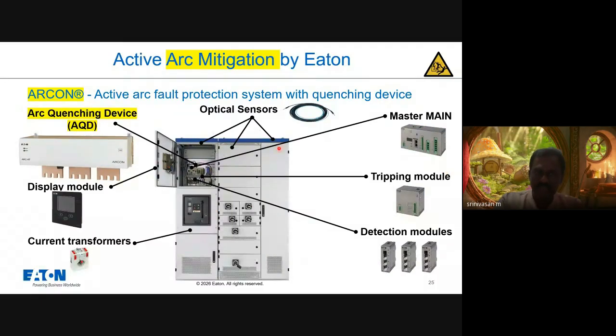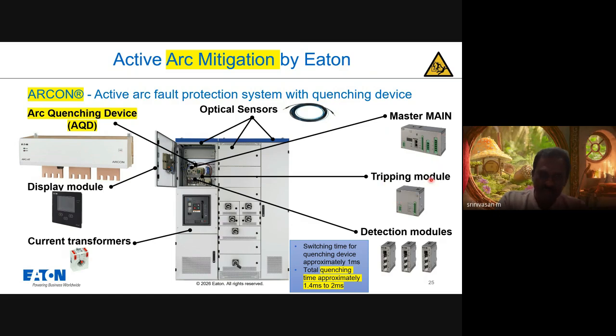The working principle is that we get input from two sources. One is the optical light sensor, and the other is the current sensor. Both inputs feed to the main relay, which evaluates them. Then it feeds the signal to the ARCON to activate, and the ARCON makes the shorting. All these activities, that means getting the input from the optical light sensors and the current sensor, the signal being evaluated by the master relay and giving the signal to the arc quenching device, and the ARCON making the shorting, all happen in less than 2 milliseconds. That means before the blinking of an eye, the action is completed. The arc is quenched in less than 2 milliseconds. That is the only thing we need to highlight.